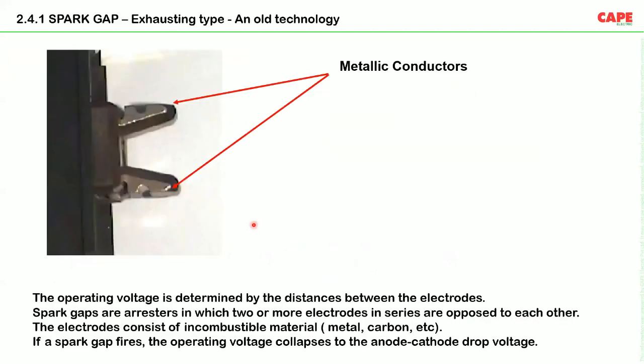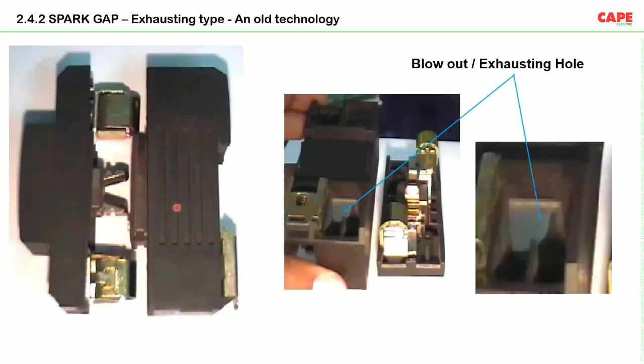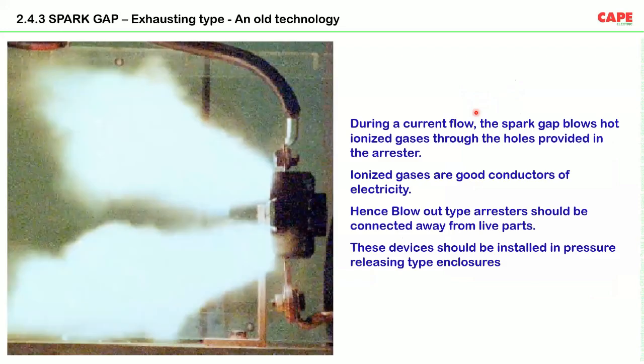Coming to spark gap, how it looks like. One of the simplest forms of spark gap is two metal electrodes and air in between. Spark over is going to happen between the electrodes or between the metallic conductors in air. One of the oldest constructions of spark gap was something like this, and you can see here the construction, and there are some holes provided on the spark gap. And how the spark gap operates is something like this.